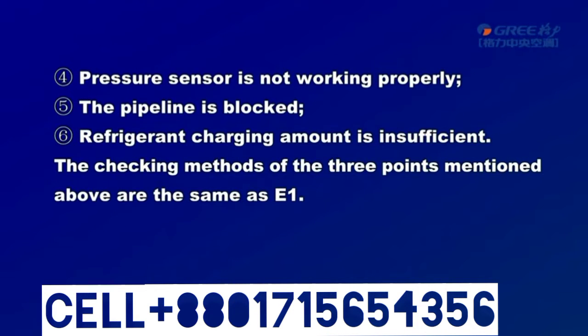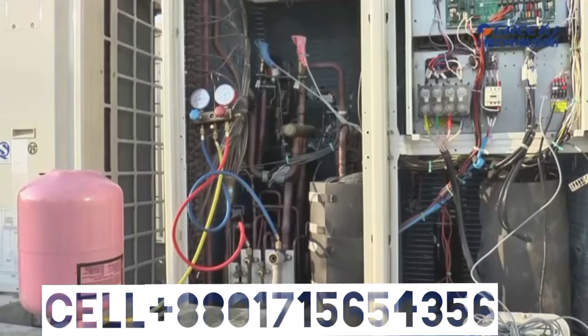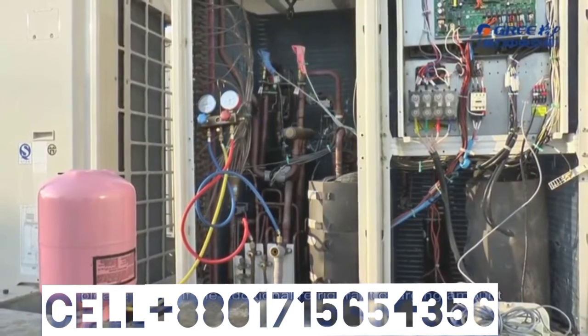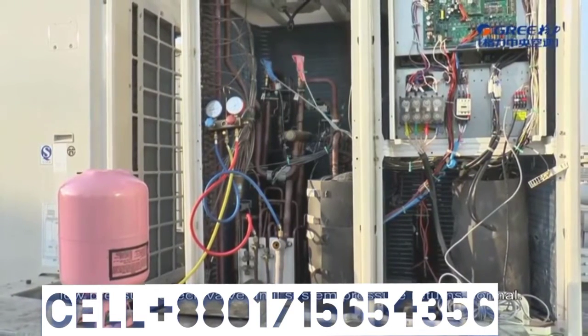4. Pressure sensor is not working properly. 5. The pipeline is blocked. 6. Refrigerant charging amount is insufficient. The checking methods of the 3 points mentioned above are the same as E1. 7. Finally, if the above-mentioned causes are excluded, please check if the additional refrigerant charging amount is correct. If it is insufficient, please charge the refrigerant from the low-pressure check valve until system pressure returns to normal. Note: do charge refrigerant from the low-pressure check valve.